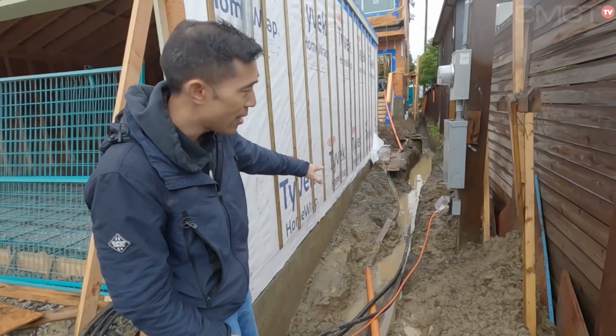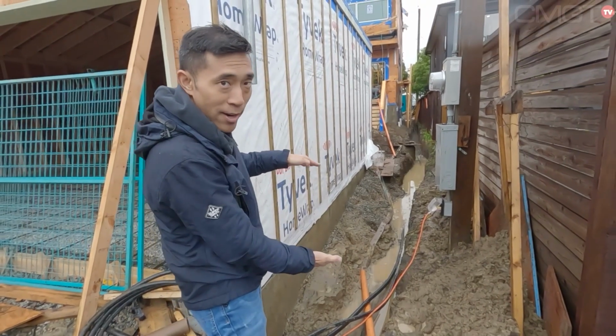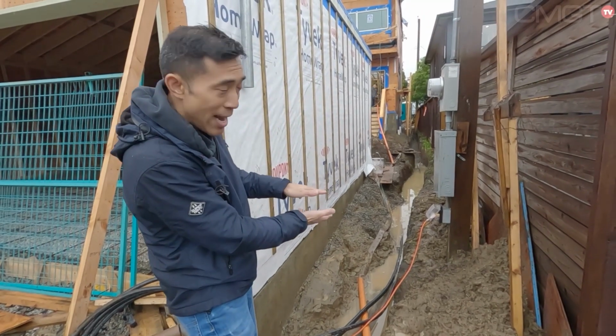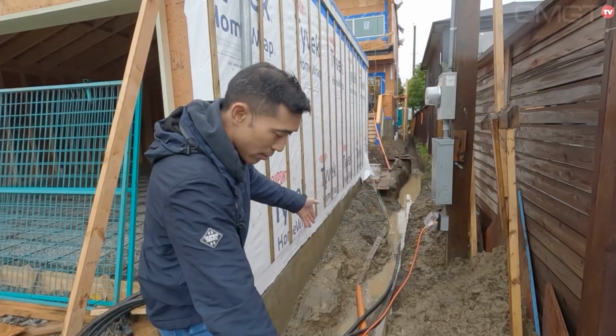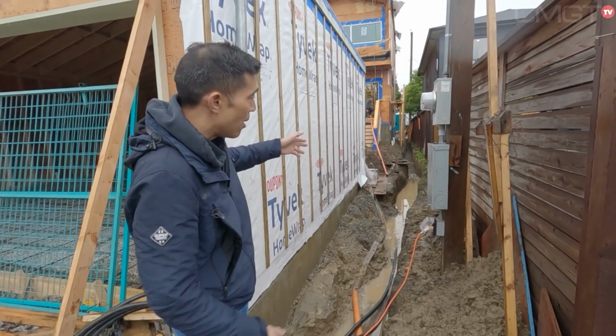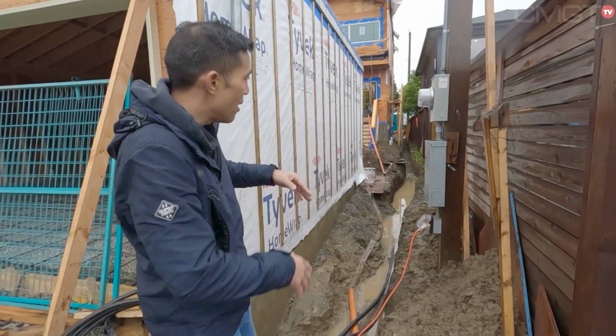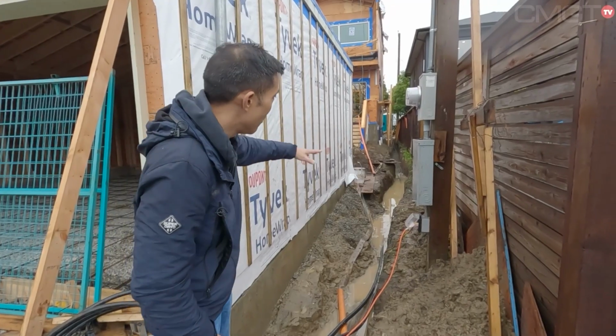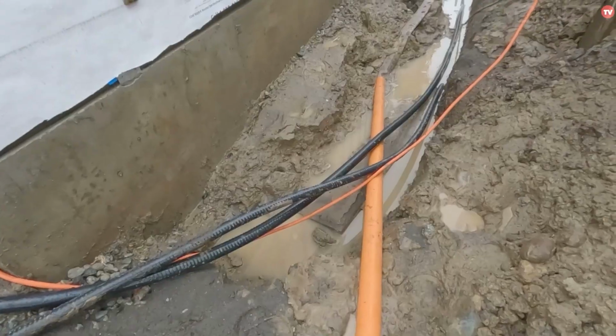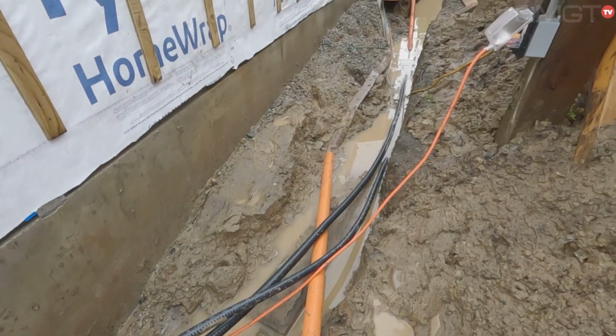Typically, when it's an underground setting, you need 24 inches of excavation with a 6-inch bed of sand. The TECK cables and the conduits rest inside that, covered further with another foot of sand and electrical caution tape, and then finally backfilled. Now this process has to be inspected because this is all underground work.